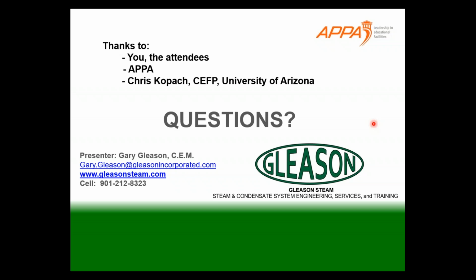Hey Gary, what do you recommend? Our university systems are dealing with F&A rates, federal government charges on our grants, auxiliary chargings of internal customers. In terms of meters on our steam system, should we be metering the steam coming in or the condensate coming out? Well, I've seen it absolutely done both ways, and I would encourage, if certain universities or folks are not metering, they should be. And the reason being is because when we meter the steam, we hold people in a particular area or even a particular building accountable for that steam usage, and they're not as likely to walk past a steam leak.